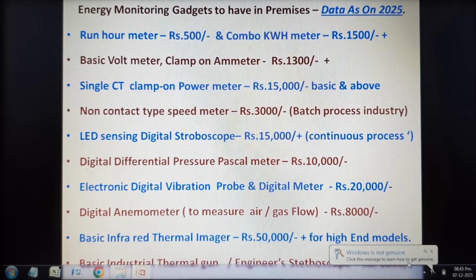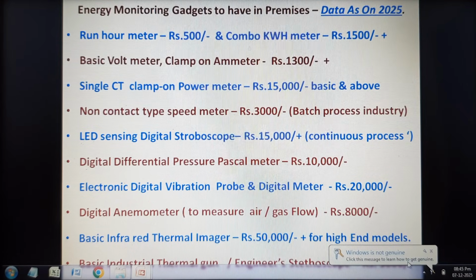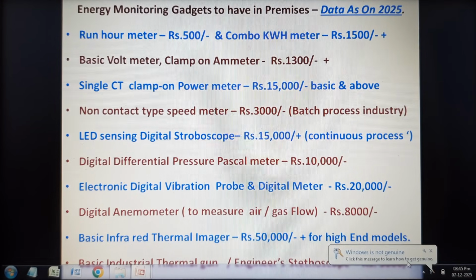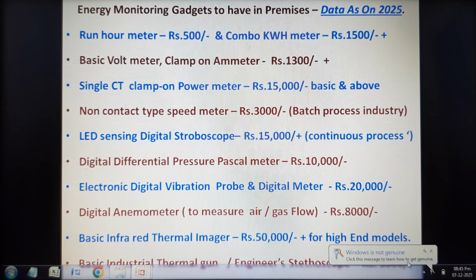The Bureau of Energy Efficiency always says monitor your kWh to target your consumption, but it is not only the input kWh. What is the deliverable quantity, in terms of Pascal, in terms of compressed air pressure, or in terms of pump pressure, whatever the deliverables may be, that also needs to be monitored. So you know whether we are operating the process at the optimum level, whether we are getting the right energy inputs given to the process, and where we can optimize that.